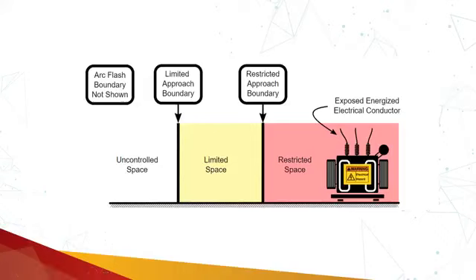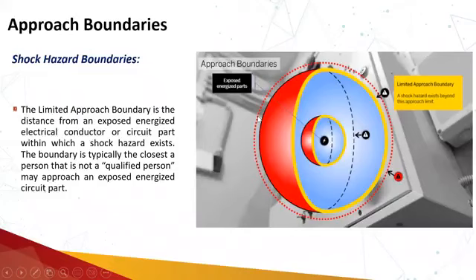What does escorted mean? Escorted means under the supervision of the qualified person. Only a qualified person is allowed to cross the restricted approach boundary and enter the restricted space, if he is wearing the appropriate personal protective equipment. So let's review the definitions of the shock protection boundaries. The limited approach boundary is the distance from an exposed energized conductor or circuit part within which the shock hazard exists. It is typically the closest a person who is not a qualified person may approach exposed energized conductors or circuit parts.